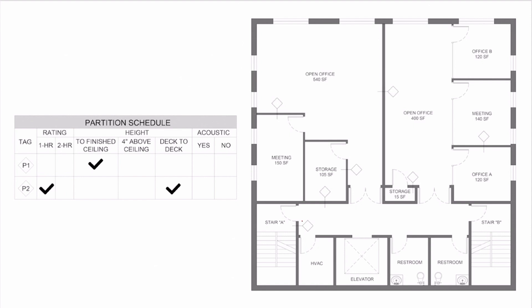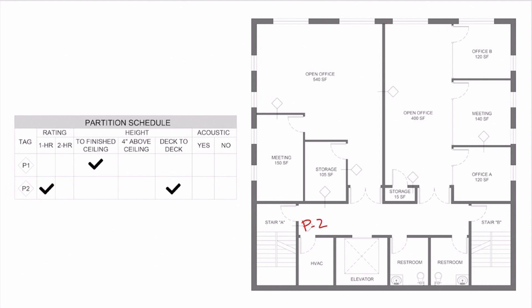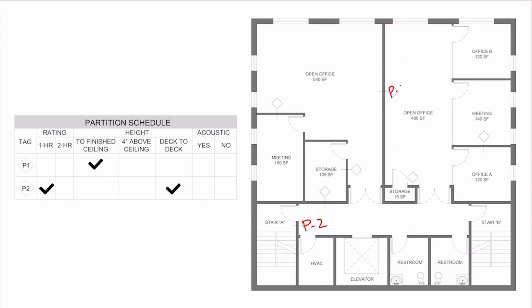Let's place the P2s in the correct spots first, and then that can help us inform what's going to be P1. We know that fire stairwells always have to be fire rated, so at Stair A we can put P2. On the actual exam it will probably be a drag and drop situation. We also know that any tenant demising walls — the wall between two tenants — are going to be P2. And any walls dividing a tenant space and a public corridor space will also be tagged P2.